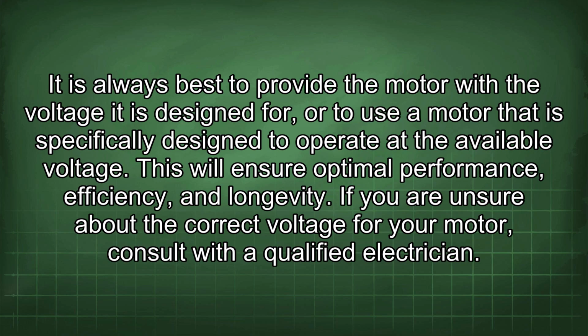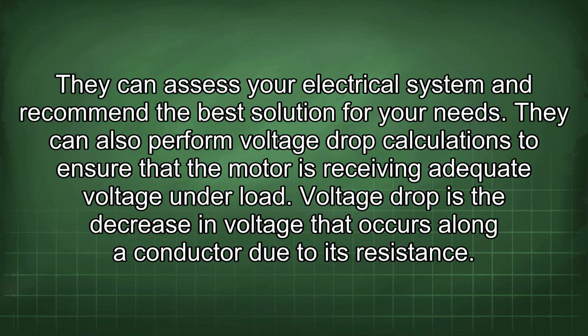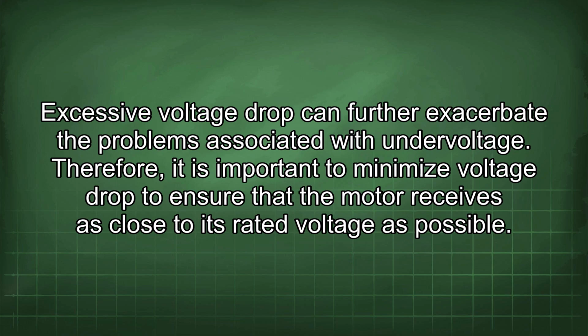If you're unsure about the correct voltage for your motor, consult with a qualified electrician. They can assess your electrical system and recommend the best solution for your needs. They can also perform voltage drop calculations to ensure that the motor is receiving adequate voltage under load. Voltage drop is the decrease in voltage that occurs along a conductor due to its resistance. Excessive voltage drop can further exacerbate the problems associated with undervoltage.